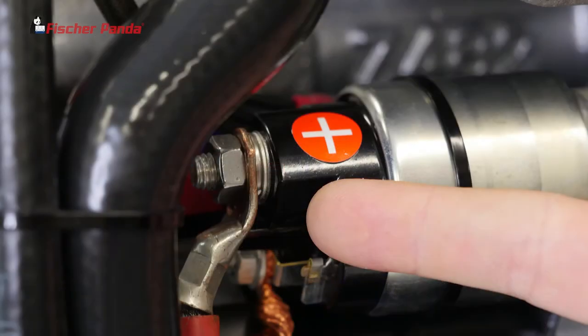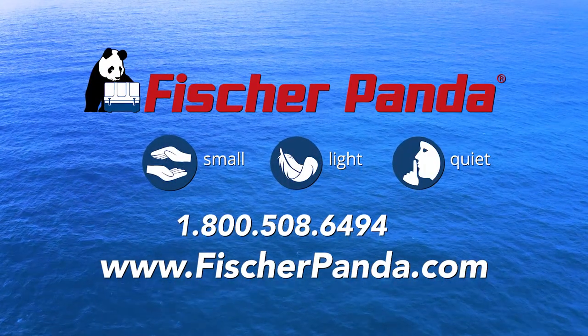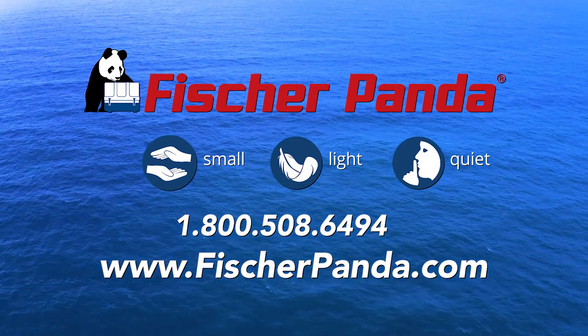Reinstall your DC power to the generator. Start your generator and check for leaks, verifying that the coolant is circulating through the expansion tank. That's how you bleed a Fischer Panda generator. For more information and further assistance, contact your local Fischer Panda dealer or our service department.